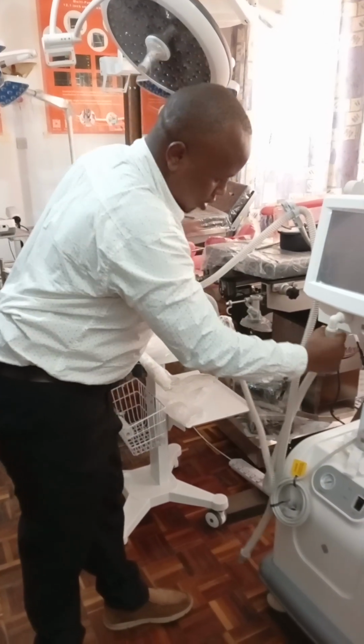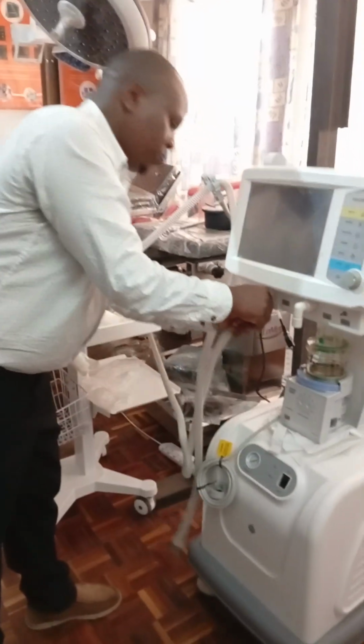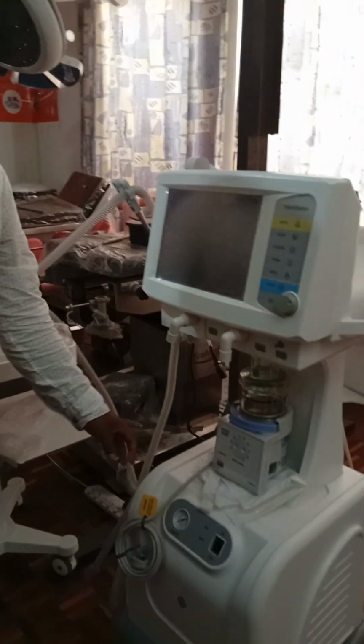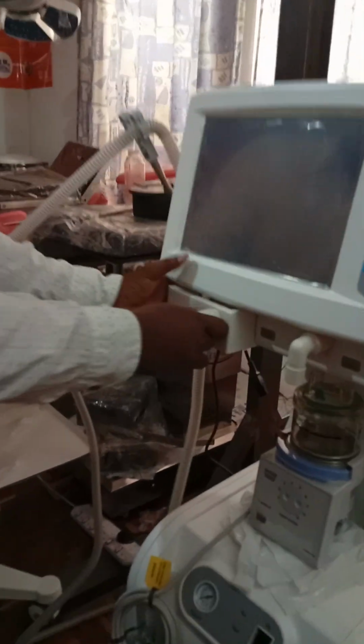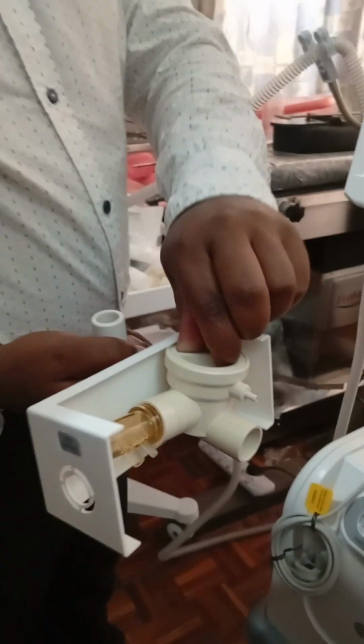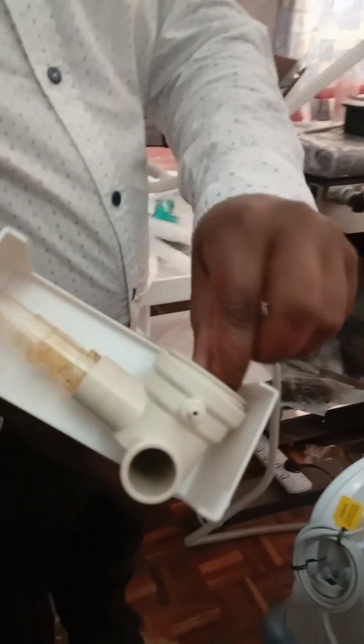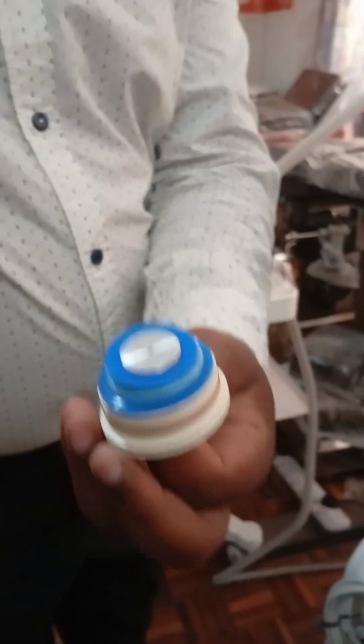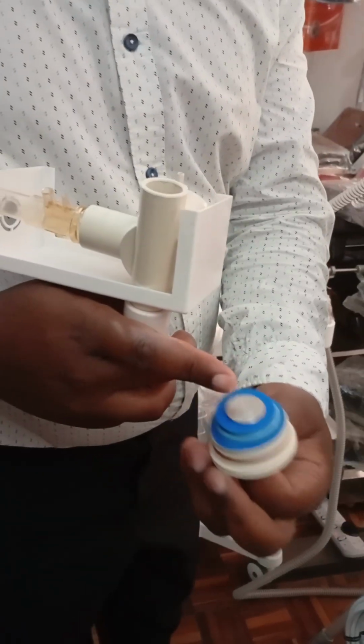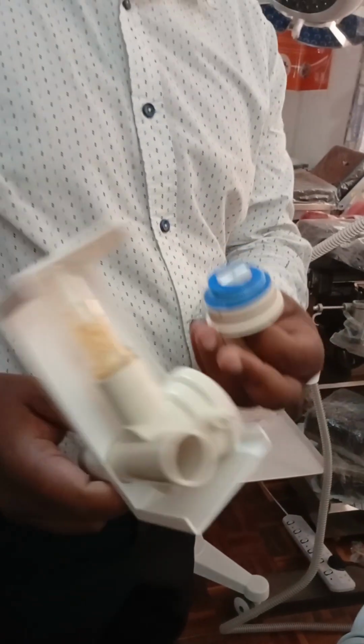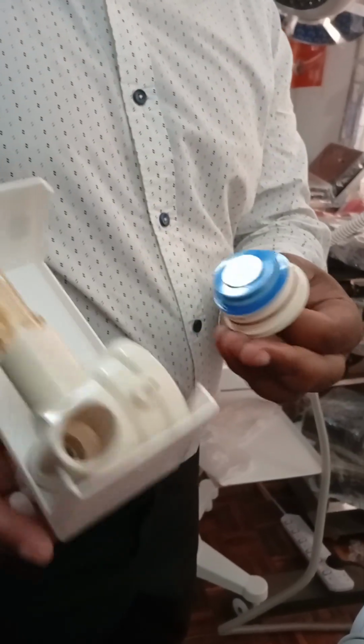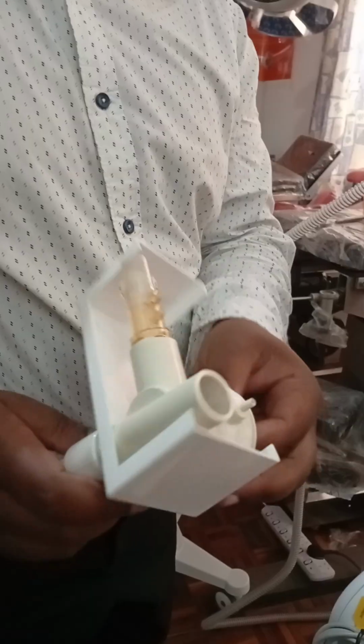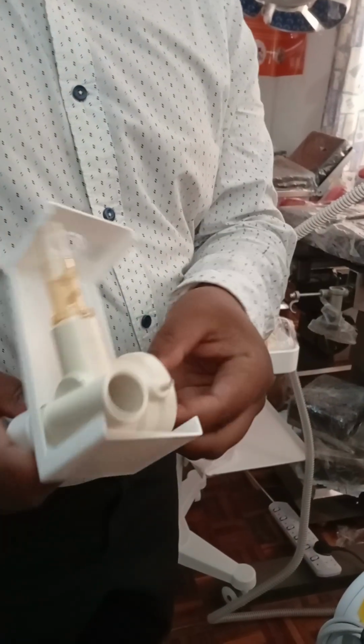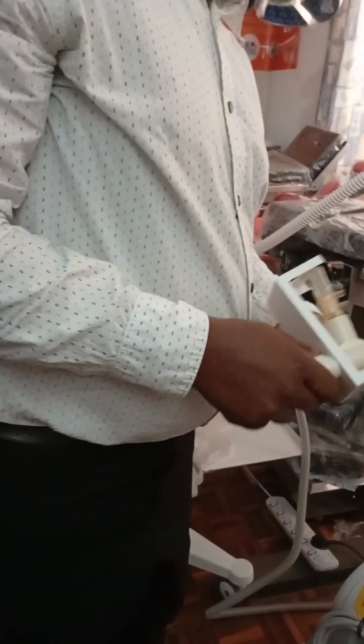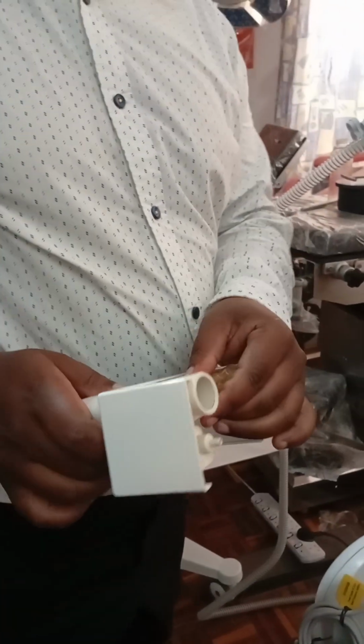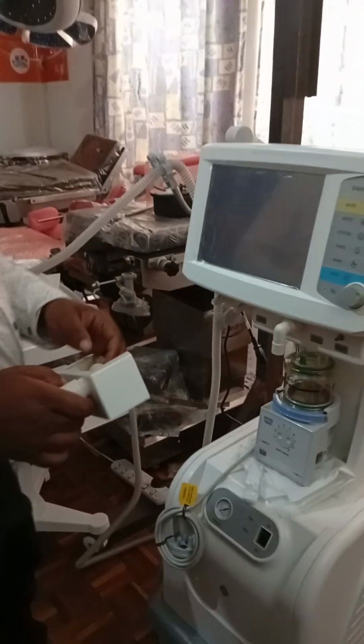Now, on this part, the most important part after use in every patient, there is a filter inside here. Usually it can even be sterilized. You need to remove and clean this upper part. You can even autoclave this one. Sterilize. So before you use it for any patient, you make sure you clean this one. But for now, since the machine is new, you don't need to sterilize. So those are the things you need to check before you start on switching on the machine and doing anything.